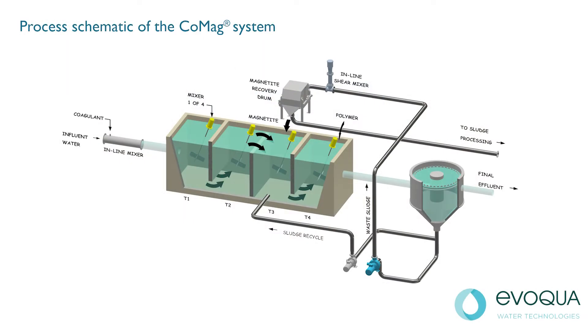This is the process schematic of the COMAG system. It comprises a series of stirred reaction tanks, which condition the water prior to it entering the clarifier, where the solids rapidly settle out to leave a very high-quality, low-turbidity treated effluent.